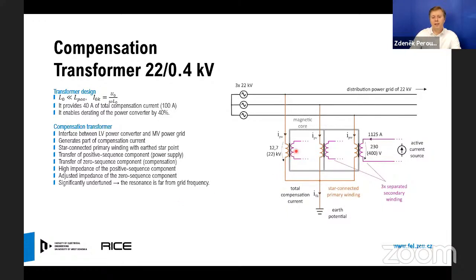The transformer is a three-phase transformer with a star-connected primary winding, whose neutral point is grounded. And we are operating three independent, separated secondary windings where our converters are connected. We came with a special design of the transformer, which makes it possible to optimize or properly design the zero sequence impedance of the transformer, by which we are able, without any intervention of the converter, to compensate part of the fault current. In this prototype, we designed the transformer in such a way that it is able to offer 40 amps of the total compensation current, which is 100 amps.